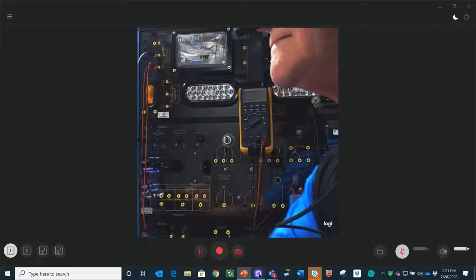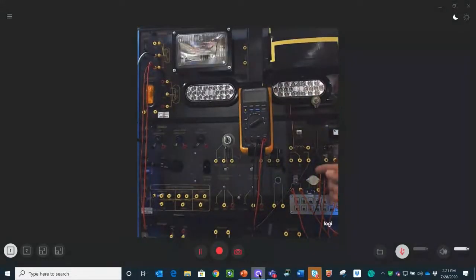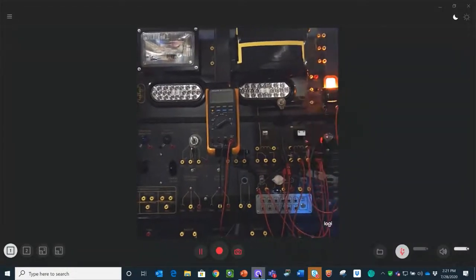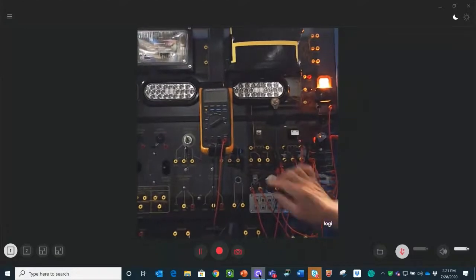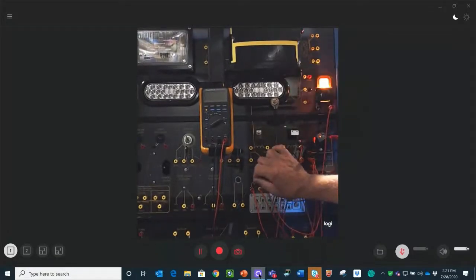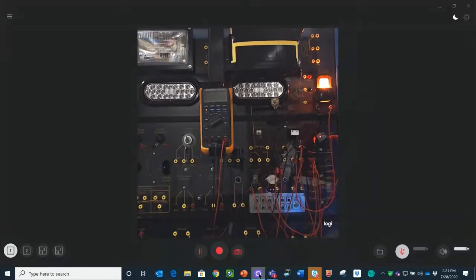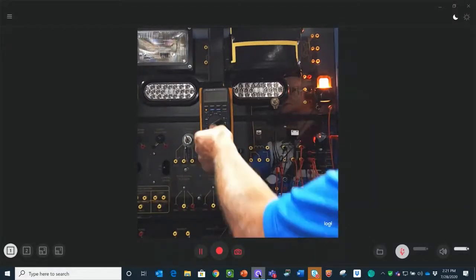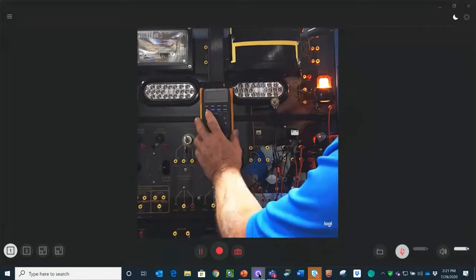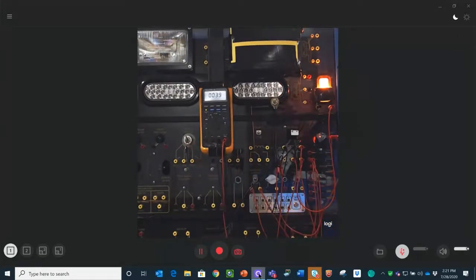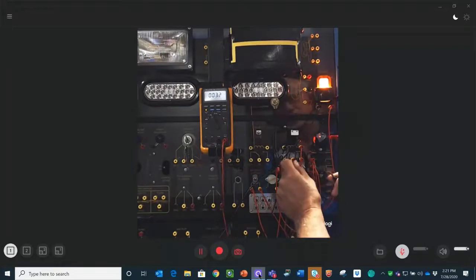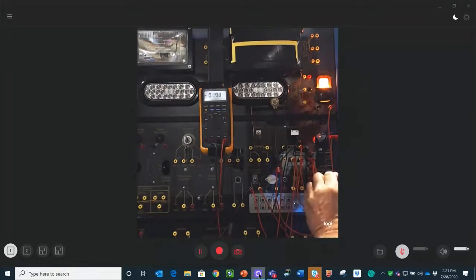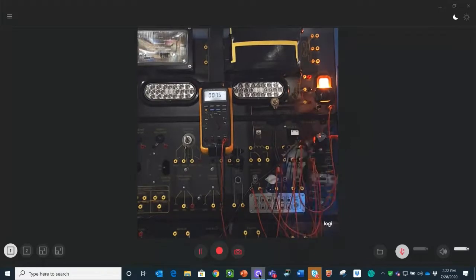Okay, if I turn my switch on right now, my marker light comes on. There you are. Switch off, switch on. Now I'm going to take my voltmeter, set it up for millivolts, turn on the light so you can see it, and I'm going to measure the voltage drop between 30 and 87. And it says 7.5 millivolts.